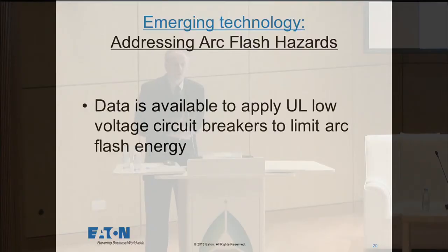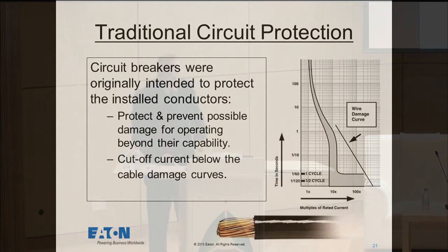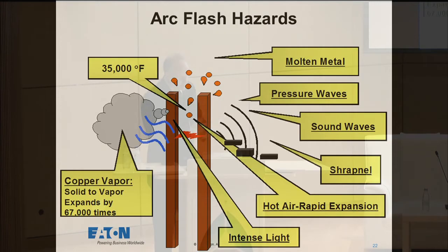Good morning, everybody, and thank you for allowing me to come back again today. Circuit Breakers has information available to you to help address arc flash. And arc flash is something that was, what happened here was, this is a cable damage curve. You would set the overcurrent protection so it would be low. Air actually becomes a conductor. What this is attempting to show is these two vertical brown pieces are conductors. Not a good drawing, but they're conductors. An arc happens because someone drops a wrench, a wire gets loose while somebody's working inside the equipment, something starts the conduction process, and then it goes by itself.